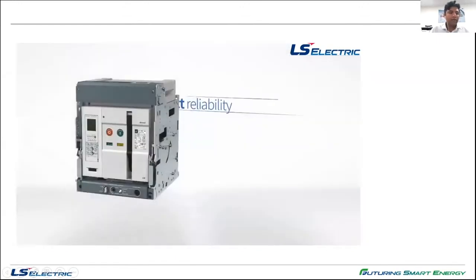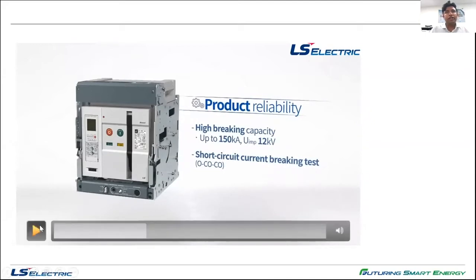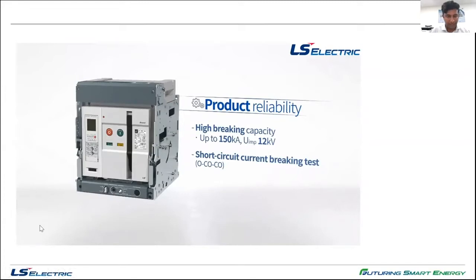Now coming to product reliability, you can see here that, as I said, we have breakers up to 150 kA, completely tested, with impulse withstand voltage of 12 kV. Normally for a low voltage switchboard, the maximum impulse withstand voltage required will be 12 kV, or even less, 10 kV or so, but our air circuit breakers can already meet 12 kV.